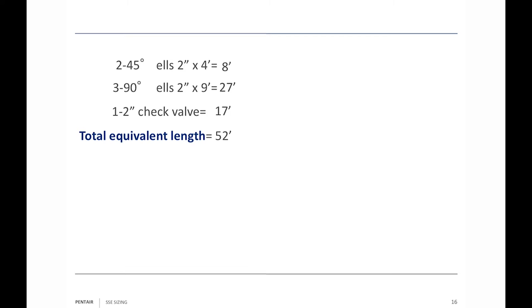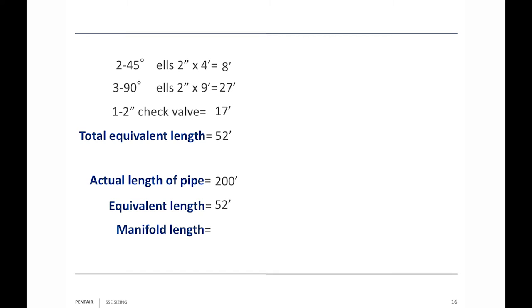Adding it all together: actual pipe length is 200 feet, equivalent length for fittings is 52 feet, plus the two-inch 30-foot manifold down the middle. Total effective pipe length for the friction loss chart is 282 feet. The friction loss chart is written in 100-foot lengths, so we divide 282 by 100 and get 2.82 hundred-foot lengths of pipe.